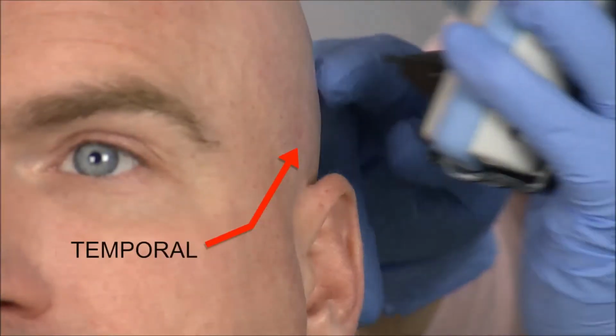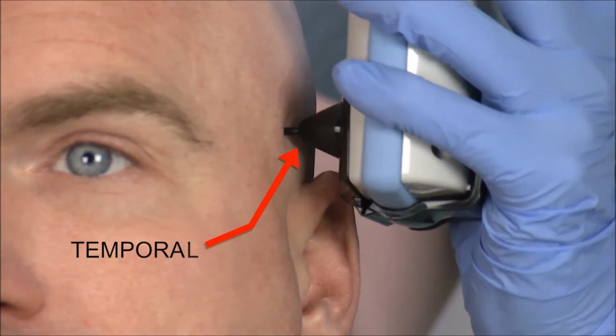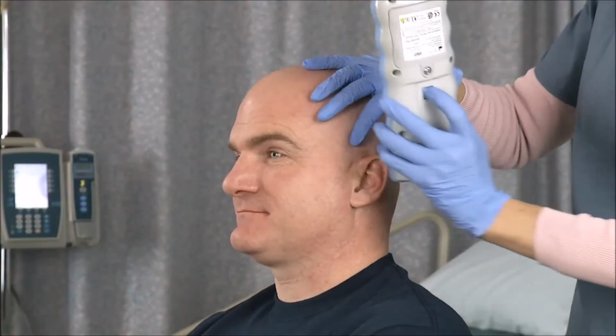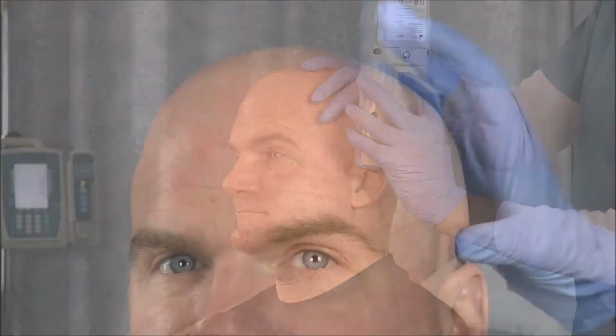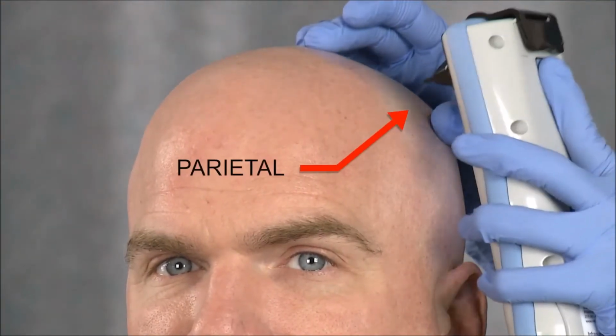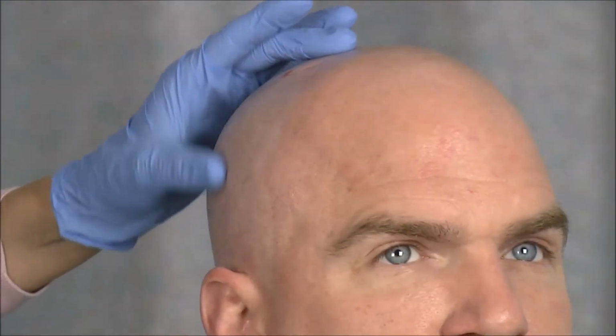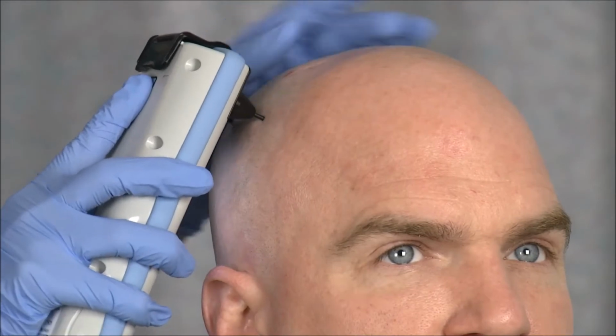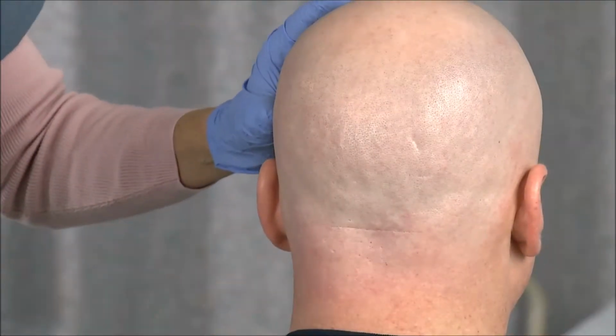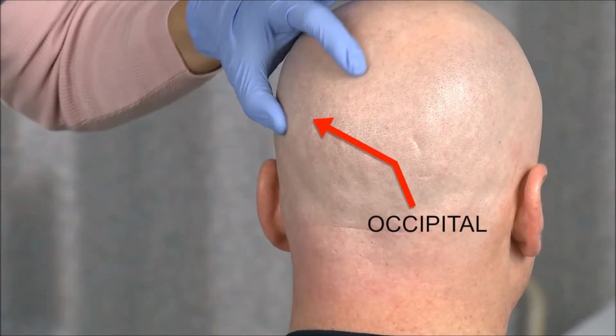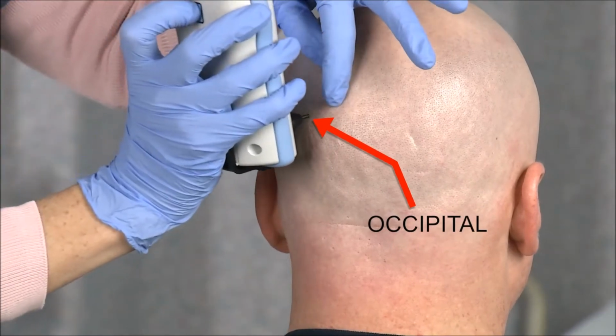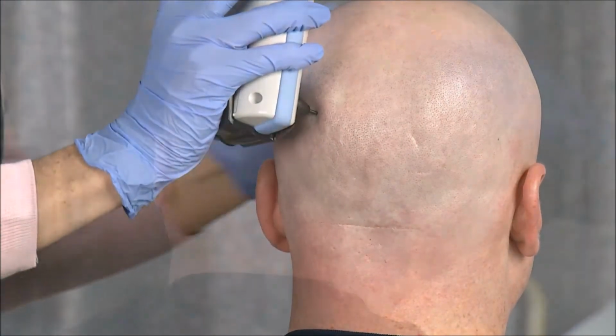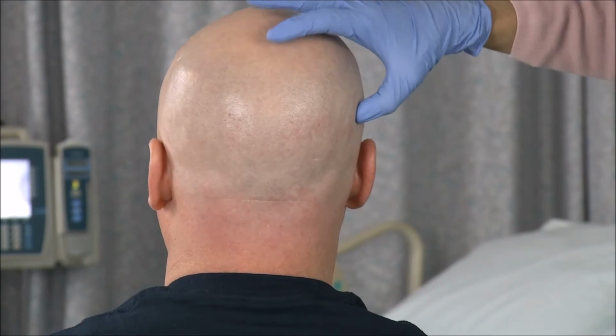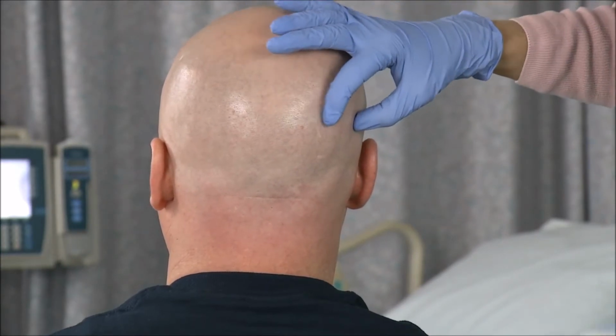For high foreheads or receding hairlines, scan approximately 4 centimeters or 1.5 inches above the eyebrow. The 2 temporal measurements are taken in the temporal fossa, keeping the unit centered over the top of the ear. The 2 parietal measurements are taken directly above the ears, midway between the ear and midline of the skull. The 2 occipital measurements are taken on the back of the head, midway between the top of the ear and occipital protuberance, 2 to 3 centimeters or 1 inch above the top of the ear.